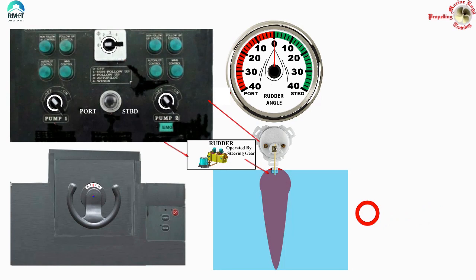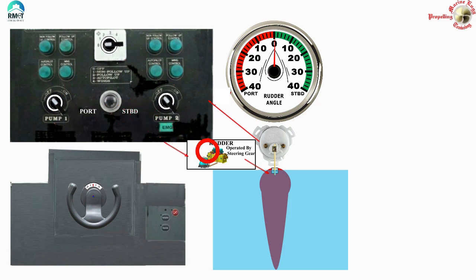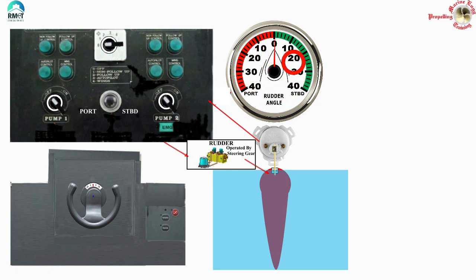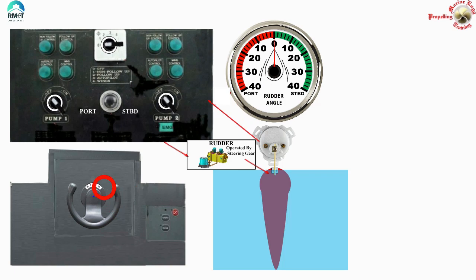Now we are going to see the operation of the steering gear in manual mode. There are two types of operation: follow-up and non-follow-up. Let us have an overview of the control panel. The system gives a signal which goes to the steering gear, and the steering gear operates the rudder. When the rudder is turning, the rudder angle transmitter picks up and gives feedback back to the system, and also drives the rudder angle indicator - the visual display seen on the bridge wings, engine control room, emergency steering flat, and on the bridge.